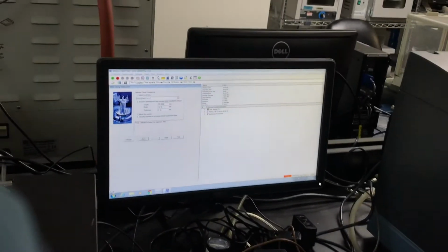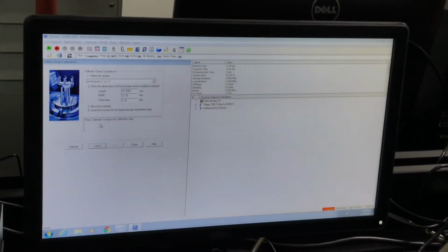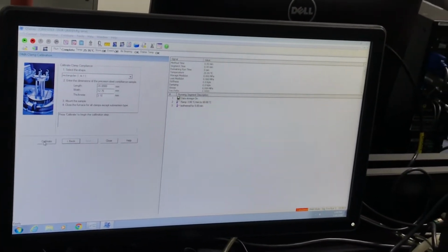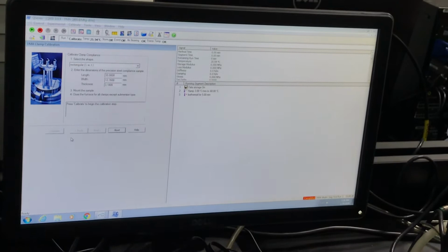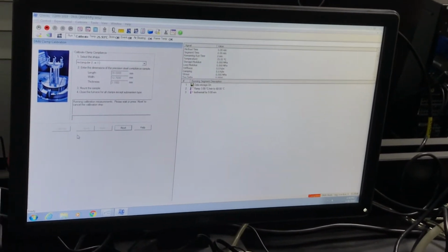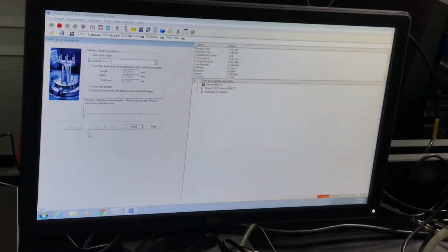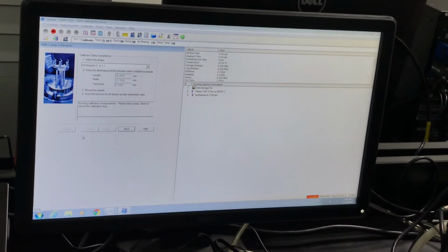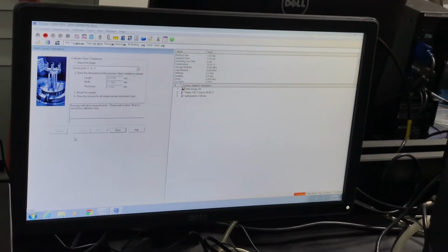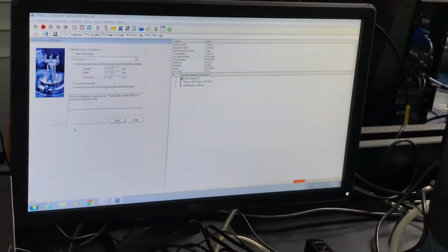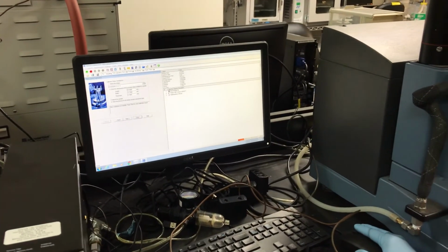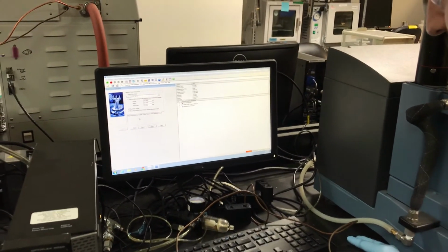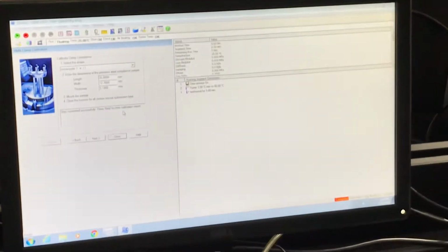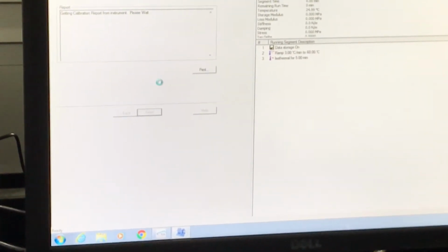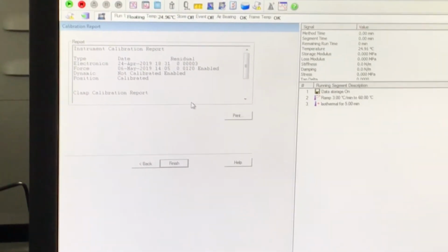So now that the furnace is closed, we can go ahead and press calibrate to begin the calibration. And this could take, it doesn't say. So this could take a couple minutes, just like the previous step. So the furnace opened back up again, and it says step completed, press next to view calibration report. So we'll hit next. Let's see.